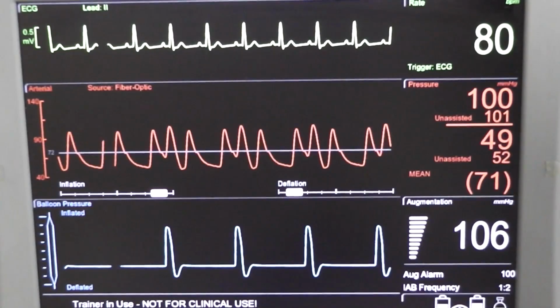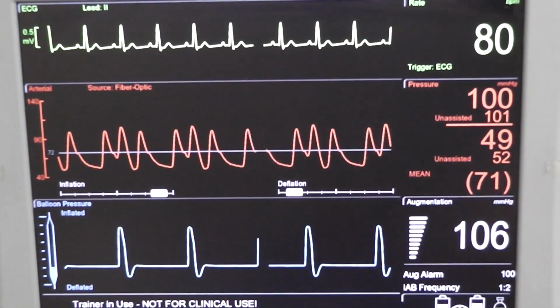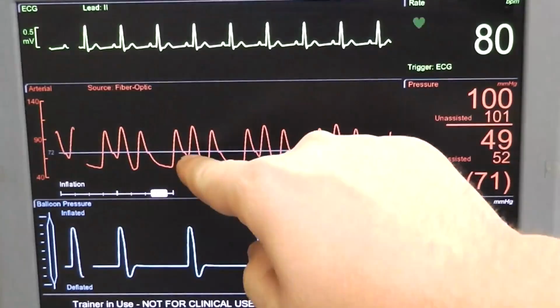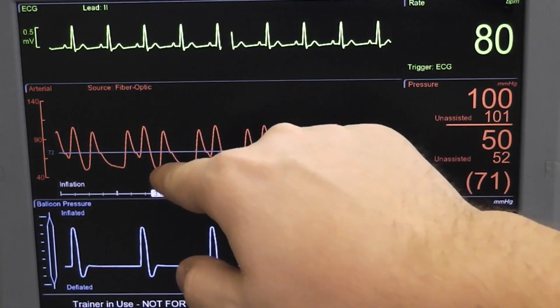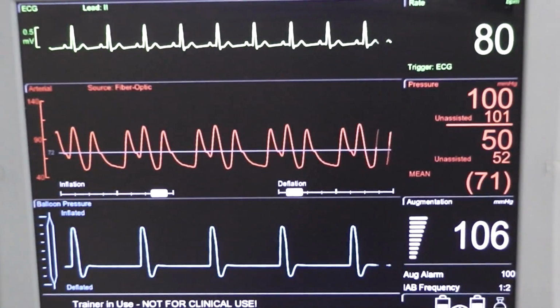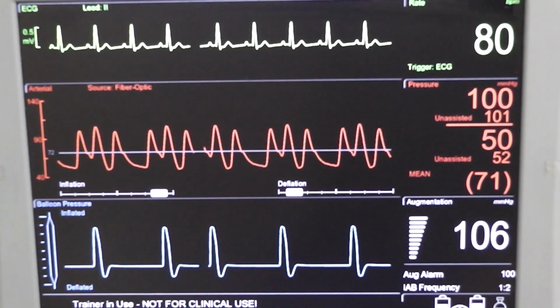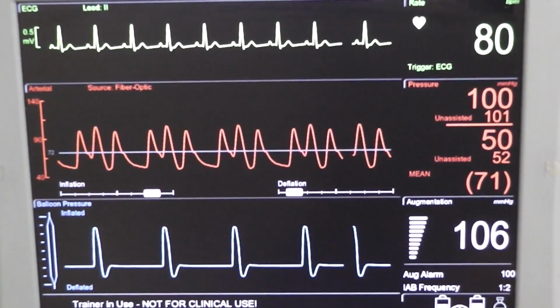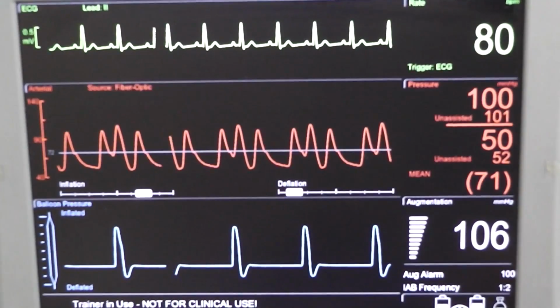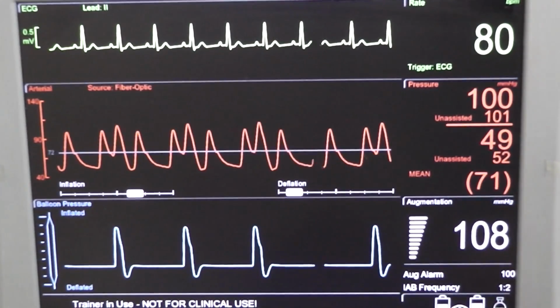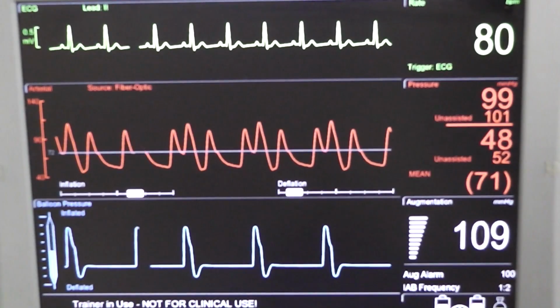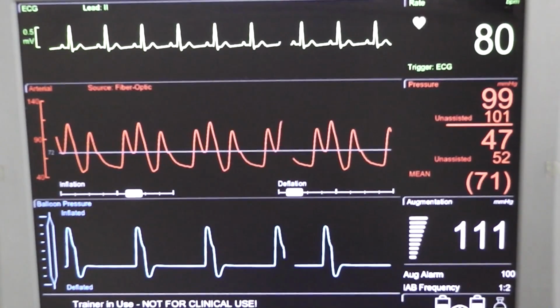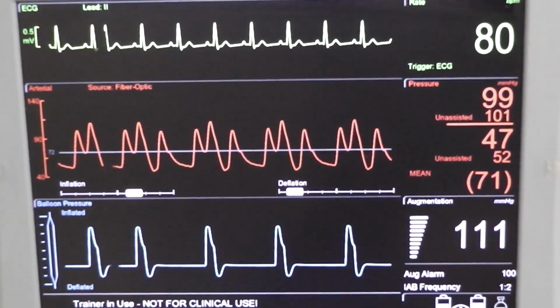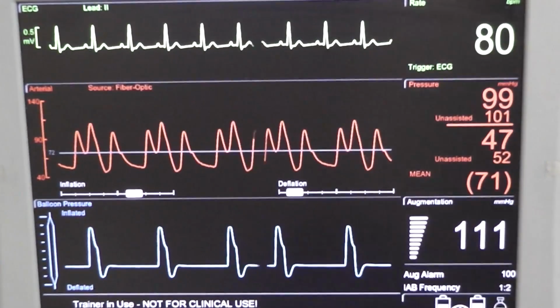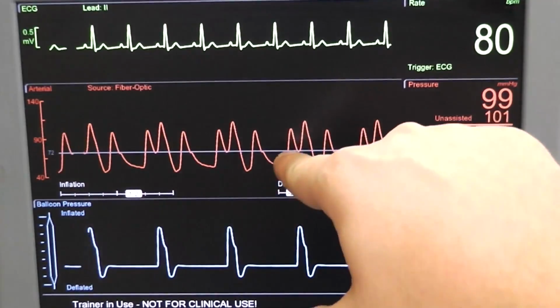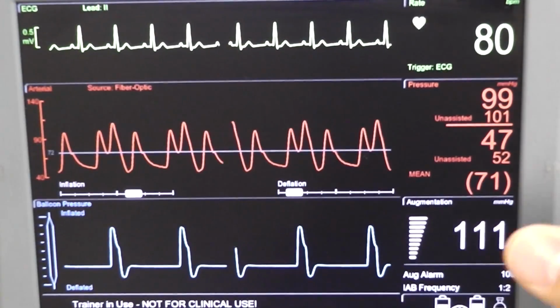And that seems about correct. So now what I want to do is move the inflation point so that the inflation occurs right at that dicrotic notch, which is going to coincide with where that line is now. So I'm going to move the inflation earlier to adjust that to that point. Okay, now I have adjusted the inflation so that it occurs right at the dicrotic notch, and you can see that it's fairly V-shaped right at that point.